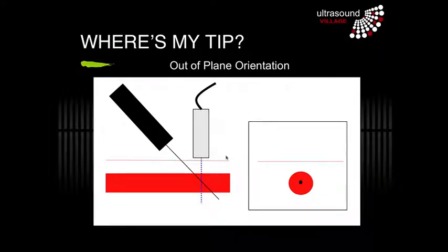But as I've mentioned, the biggest problem is that if you let the tip go a little bit too far, or you fail to see it, what you might wind up with is a beautiful image on the screen, thinking that your needle is right in the middle of the vessel, whereas in fact your tip has gone too far. And if there's something down here that you were trying very hard not to hit, well, you might have just caused a disaster.